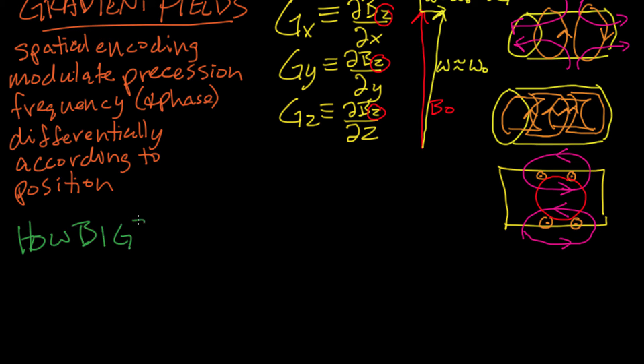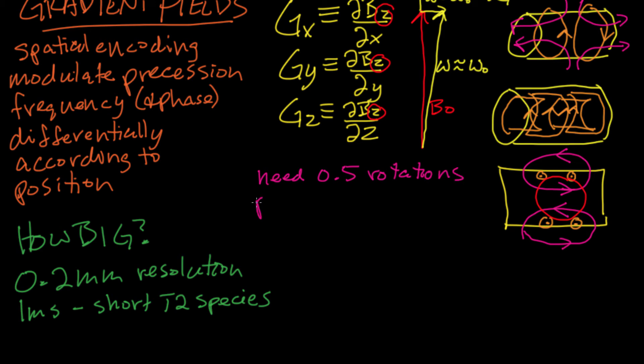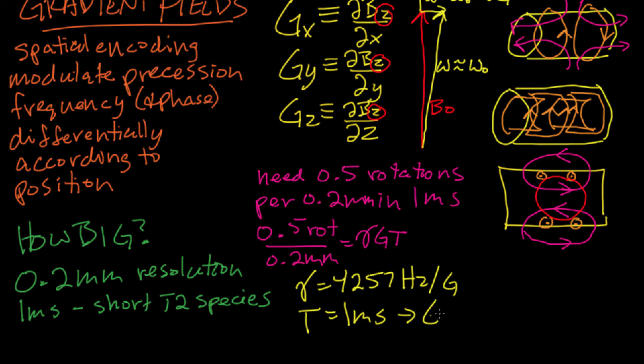Okay, so let's get an idea of how big we would like those gradients to be. So let's say we want to do a scan with 0.2 mm spatial resolution, that's very high resolution, and we want to achieve that resolution in about a millisecond, because there are some short T2 species that require very fast scanning like that. The Fourier sampling theorem says we need a half a rotation per pixel. So a half a rotation per 0.2 mm is our k-space excursion. That equals gamma times the gradient times time. Gamma is about 4 kHz per gauss for protons. So for a time of one millisecond, we need a gradient of about 5 gauss per centimeter, which is about what modern systems can produce.